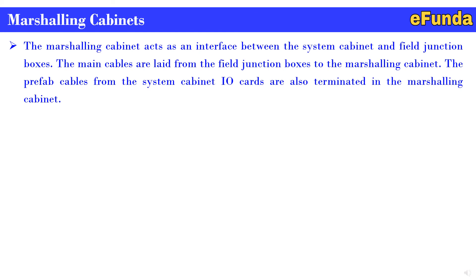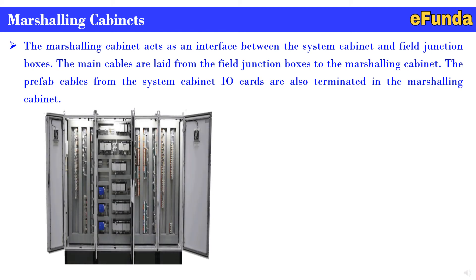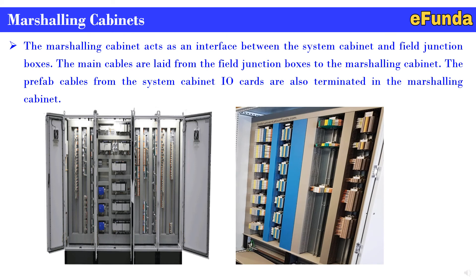The marshaling cabinet acts as an interface between the system cabinet and field junction boxes. Main cables are laid from the field junction boxes to the marshaling cabinet. Prefab cables from the system cabinet I/O cards are also terminated in the marshaling cabinet. The photograph shows a vertical 2-meter height floor-mounted panel where components are arranged in sequence to perform the interface from field to system cabinet. Another photograph shows the terminal boards and further connections to isolators.